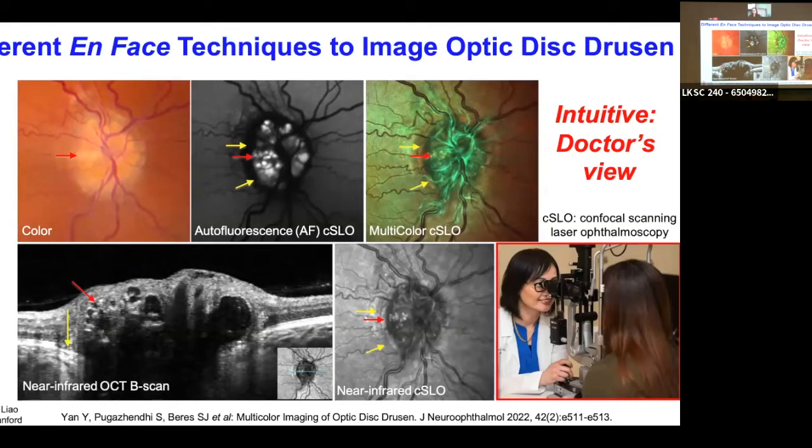And then you have the near infrared reflectance imaging in the middle on the bottom. So the wavelengths for the near infrared reflectance is essentially the same as a spectral domain OCT. So a little over 800 nanometers. And so bright things, this is also something else that Dr. Dubra taught me. Things that are bright on the OCT will also appear bright on the en face near infrared reflectance. So you really get a lot out of those images.